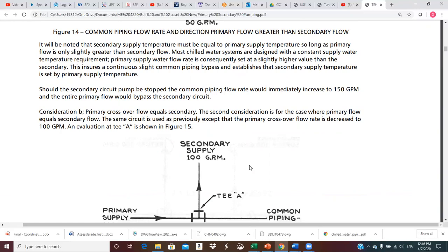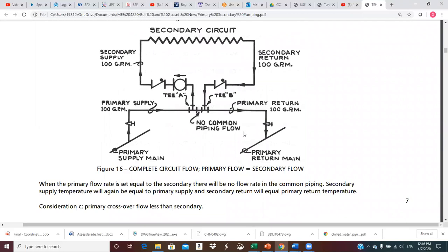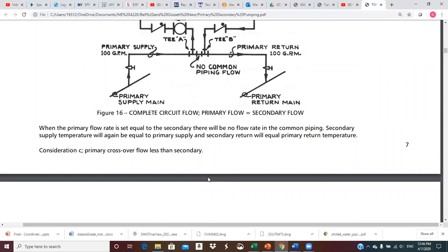Consideration B: primary crossover flow equals secondary flow. With 100 GPM in, all of it goes to the secondary — there is no flow in the common piping. A hundred GPM goes through the secondary, returns 100 GPM, and all 100 returns into the primary return main. When primary flow rate is set equal to secondary, there'll be no flow in the common piping, and secondary supply temperature will equal primary supply temperature while return temperatures are also equal.